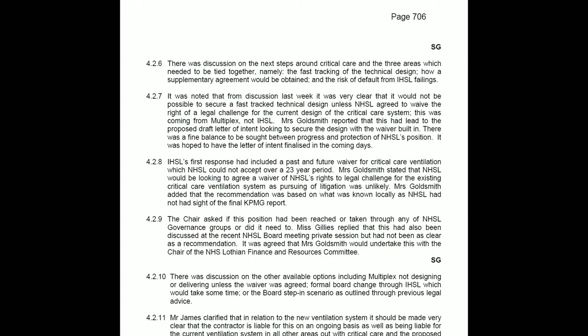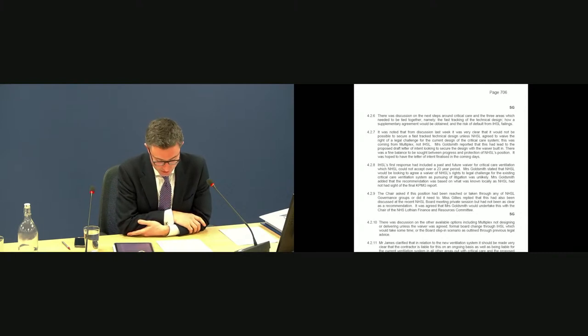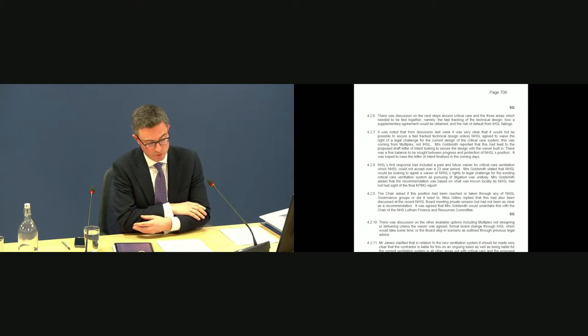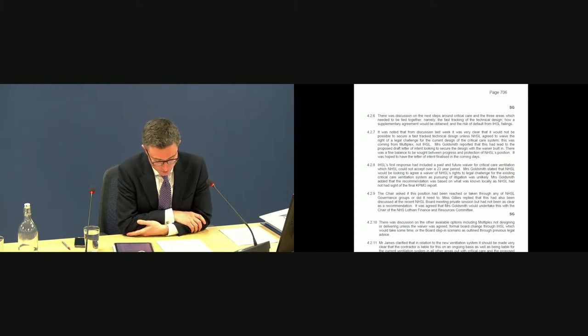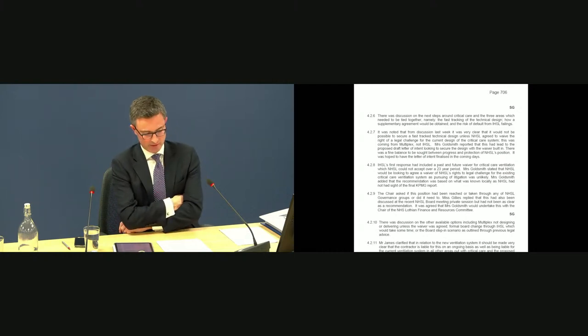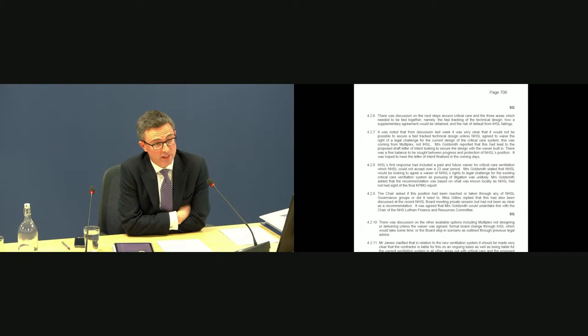Now, we understand from other evidence that the choice of those particular parameters, 10 air changes per hour and 10 pascals of pressure, was perhaps not entirely straightforward. The designers, as you may know, held the view then and continue to hold it now, that the critical care ventilation they designed at 4 air changes per hour with balanced pressure was compliant with guidance. Were you aware of that when you were on the Oversight Board?